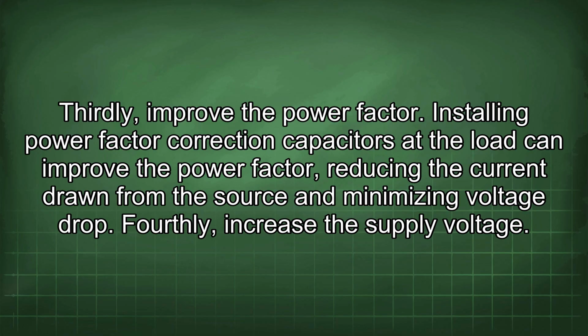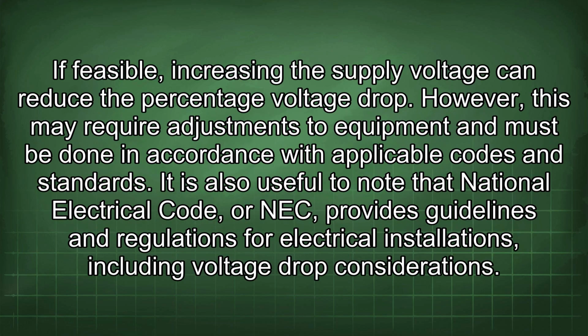Installing power factor correction capacitors at the load can improve the power factor, reducing the current drawn from the source and minimizing voltage drop. Fourthly, increase the supply voltage. If feasible, increasing the supply voltage can reduce the percentage voltage drop. However, this may require adjustments to equipment and must be done in accordance with applicable codes and standards.